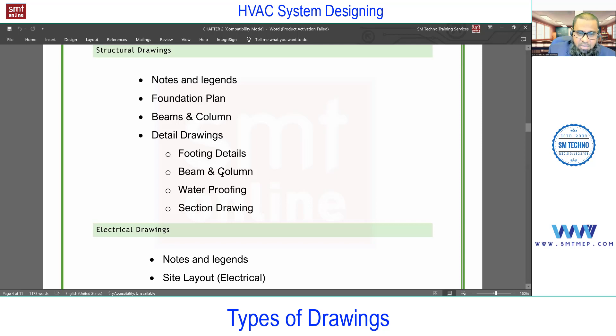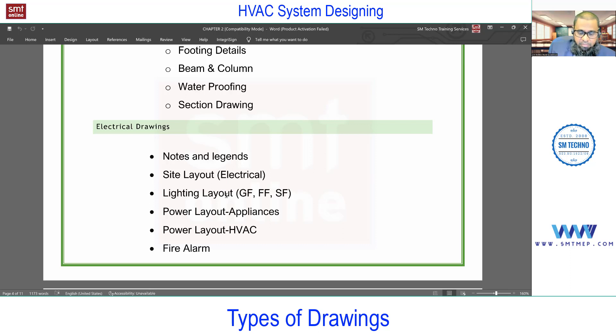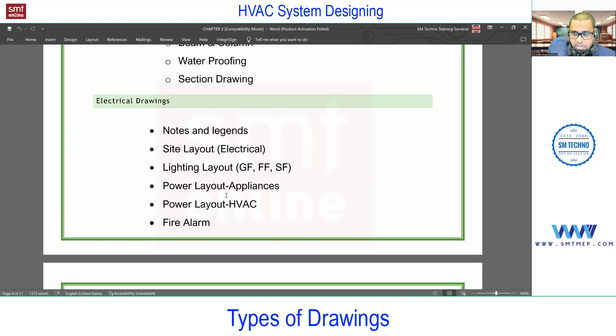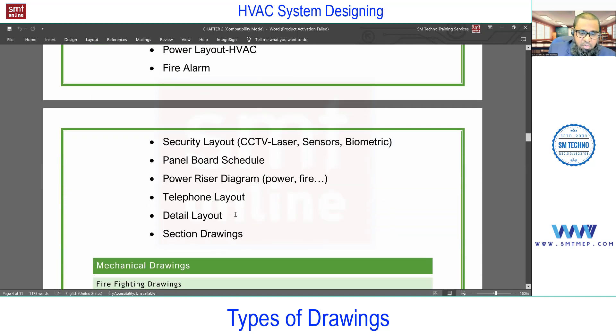Detail drawings for footings, beams, columns, waterproofing, and section drawings are given for information, but beams and columns are particularly required for coordinating duct and pipe routing. For electrical drawings, you'll find notes and legends, site layout, and lighting layout. The lighting layout is required when placing air terminals, to understand the location of light fixtures in the false ceiling so that areas occupied by fixtures are avoided. Power layout is required for appliances and for HVAC equipment loads, which the electrical team uses to calculate mechanical equipment power requirements.